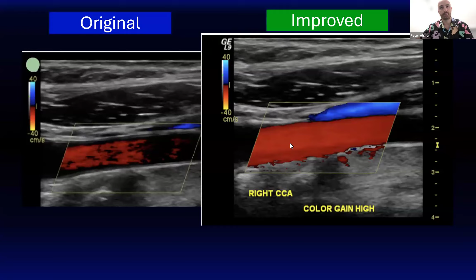And then the other example that's kind of analogous is where we're changing the scale and the wall filter. Maybe in this case, I've tried changing the gain and it really doesn't look like it's changed at all. There's zero flow in here. So in this case, I realize I need the machine to be more sensitive to that flow, and that's why we need to change these things. These things are adjusted by changing the machine preset, but you can also change them individually if you're goofing around in the machine. Thank you.